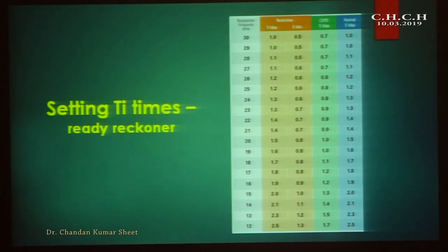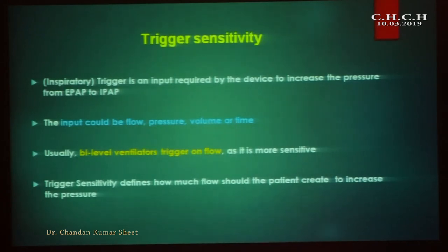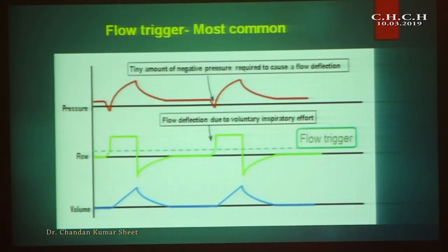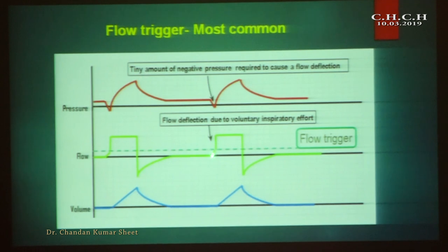Trigger sensitivity: trigger means the transition from EPAP to IPAP, determined by the patient — it may be flow, pressure, or volume dependent. In bi-level ventilators, triggers are usually flow-based because flow is more sensitive than pressure. The negative pressure generated by the patient is detected by the ventilator, which then delivers IPAP. The flow generated by the patient is sensed by the ventilator, which then gives a breath.